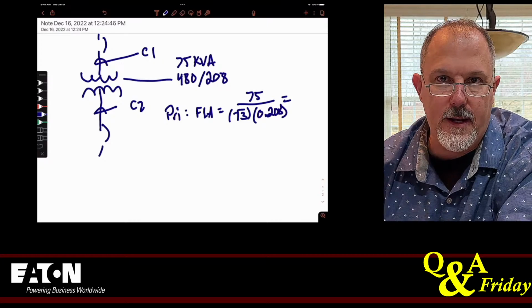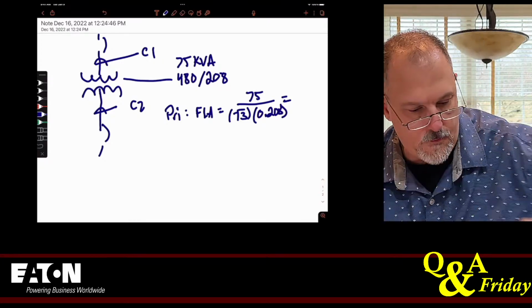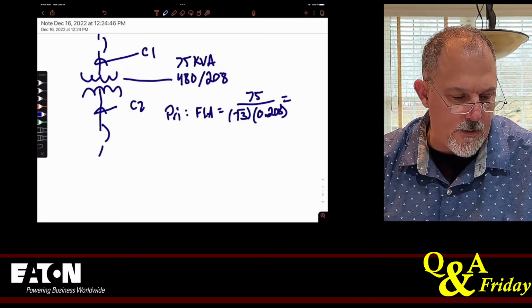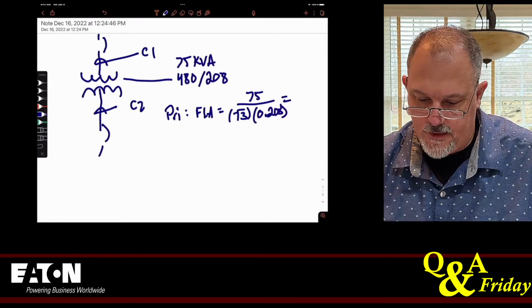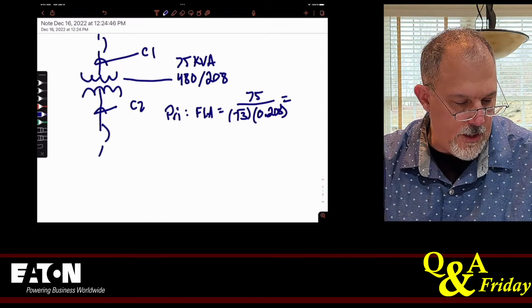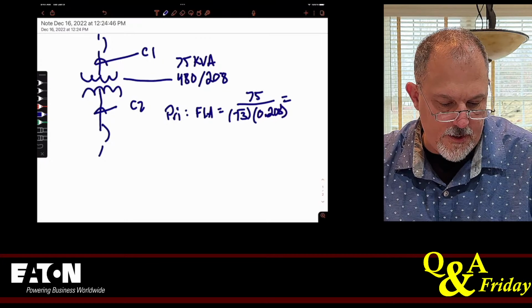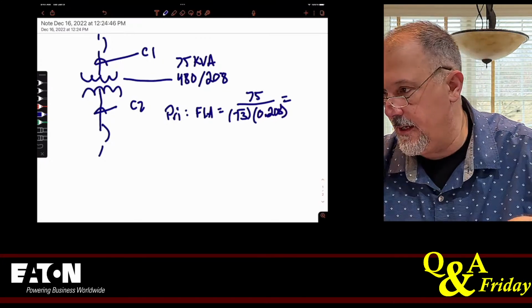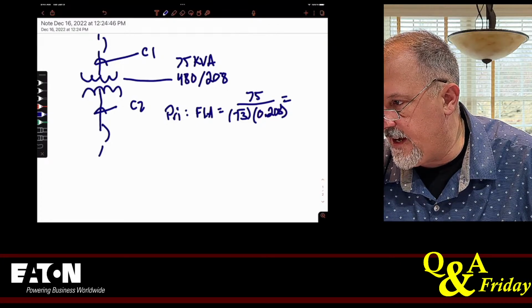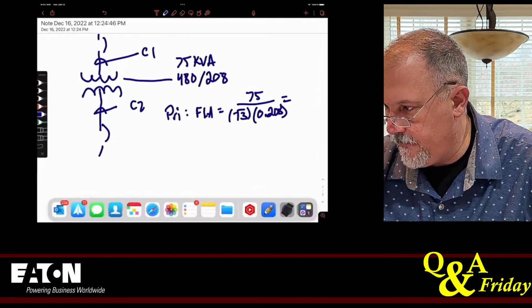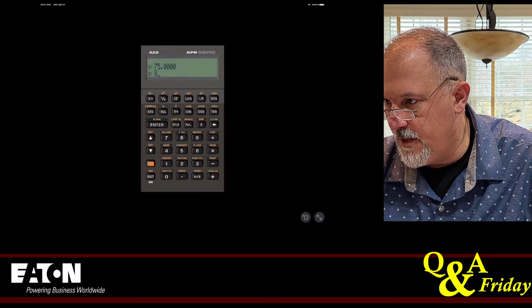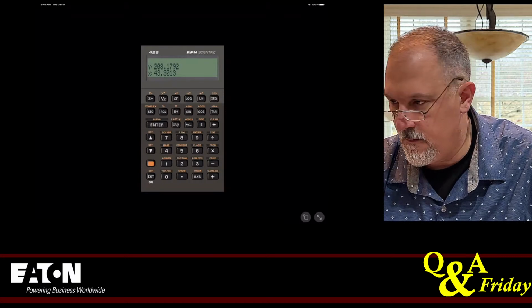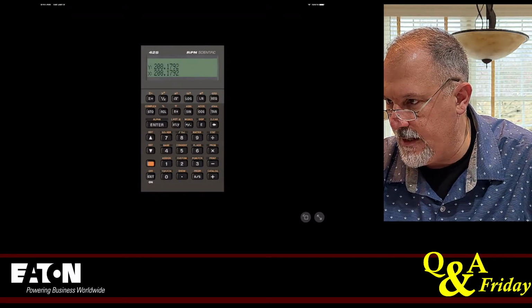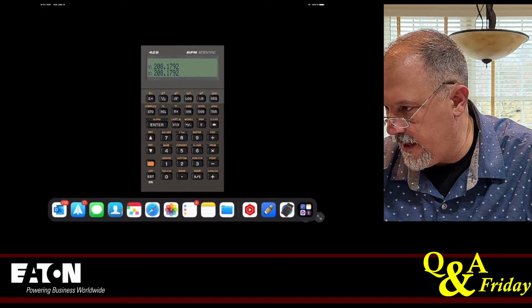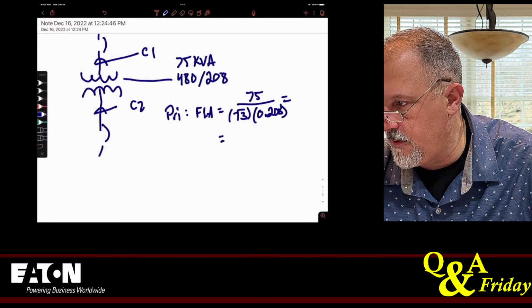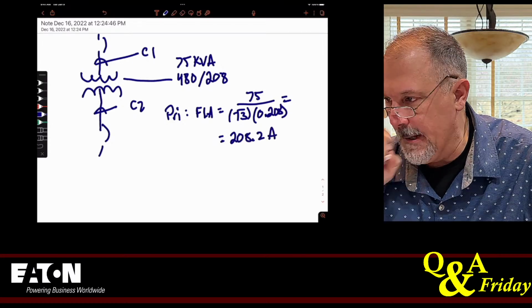I can't remember what I ended up with, but let's talk about the secondary. 450 is going to tell me my largest secondary overcurrent protective device. So I go to my tables, primary and secondary protection, and my secondary protection can't be more than 125%. So my secondary full load amps is 75 kVA divided by the square root of 3 divided by 0.208, which equals 208.2 amps.